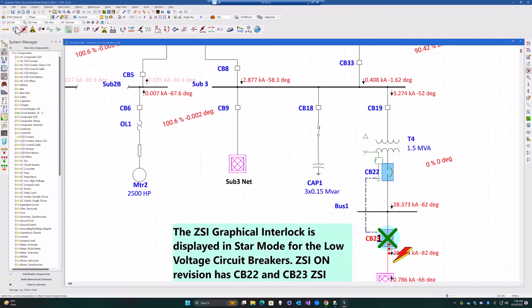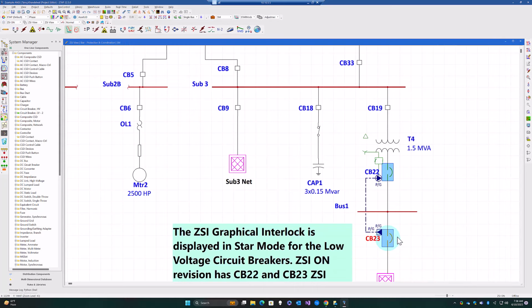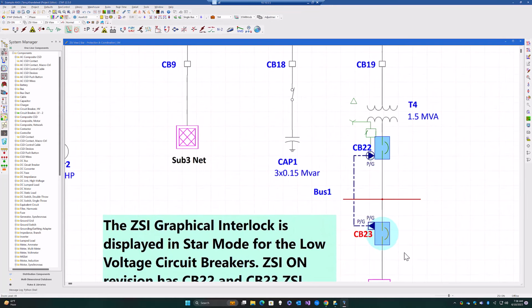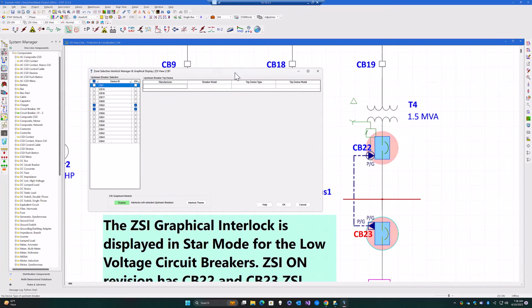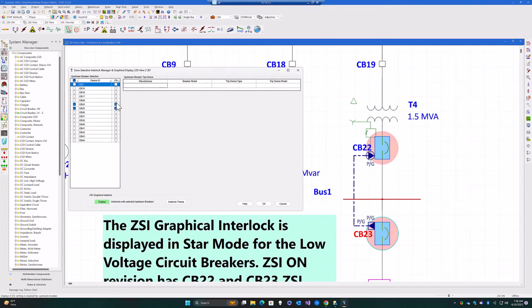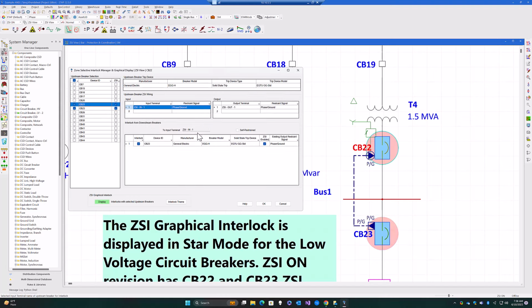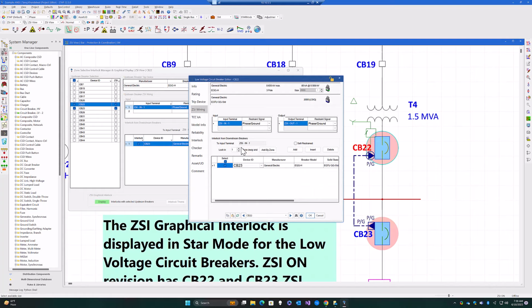So let me go ahead and quickly reset here, and we can see our ZSI wiring visualization itself. So again, when I open up the ZSI manager, we can see in our revision these two are checked, and that's because I have my ZSI input and output terminals wired. They have been interlocked with the upstream device, and we can of course double click on the breaker itself, and we can make certain adjustments as needed.